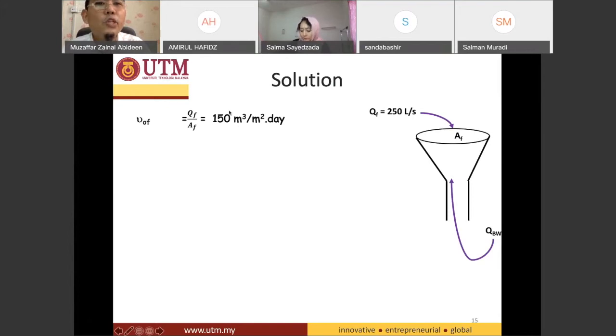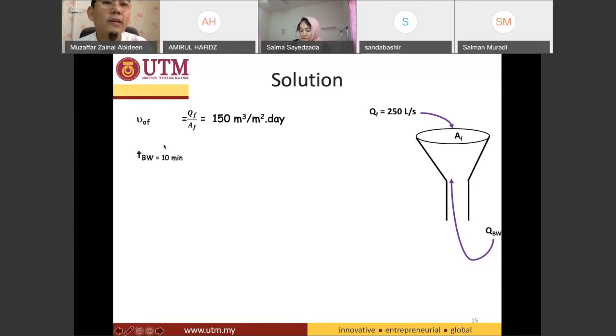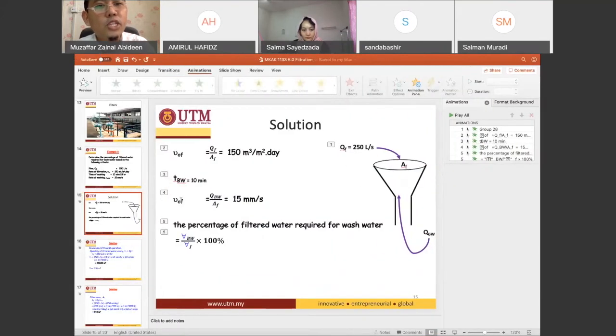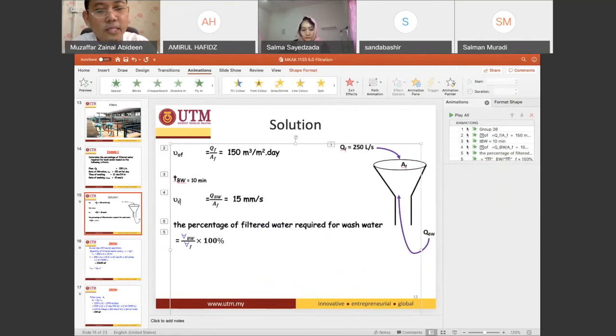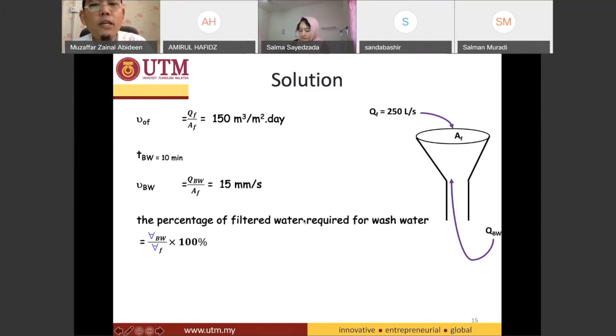The rate of filtration equals 150 meter cubed per meter squared per day. Another piece of information given is the time for backwash — only 10 minutes in a day. They have also given us the rate of backwash. I need to correct the label here — it should be BW for backwash. So the rate of backwash is q_backwash divided by af, equal to 15 millimeters per second.